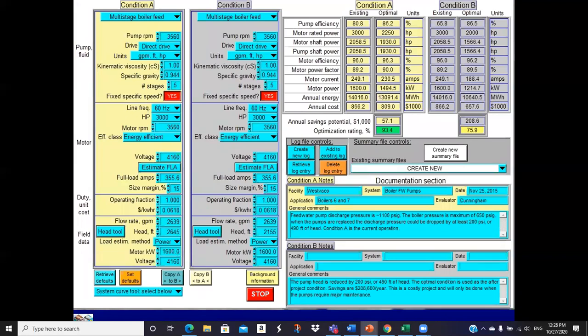So that's the screen, and we punched around on this the other day, so I'll hit this fairly quick. We've got two different conditions, A and B, just two separate analyses. It can be whatever, it's up to the engineer running the thing. They could be two separate pumps. They could be different operating scenarios for the same pump. It's up to the person putting the numbers in. We have the pump fluid information, motor, the operating fraction, how many hours it operates a year, the cost of electricity, and then this is your field data: a flow rate, a head, either power or motor current, and a voltage. And then we get results over here.